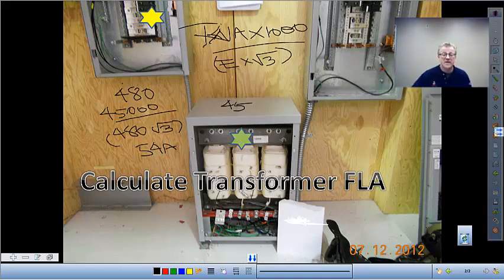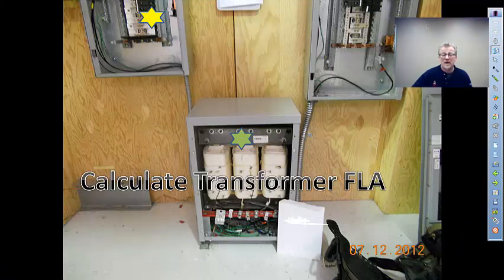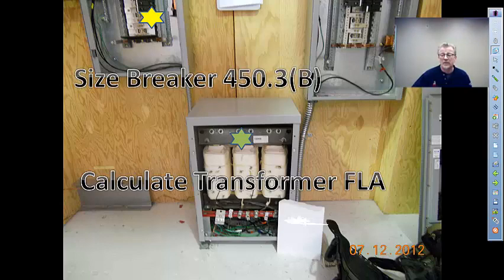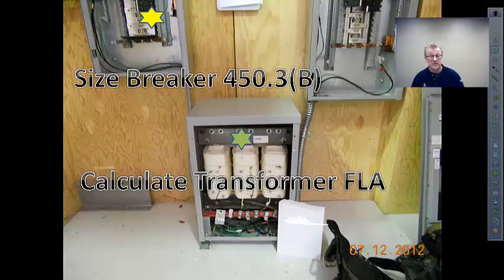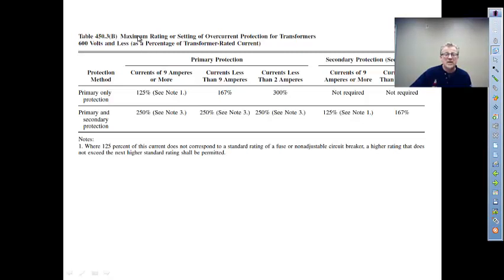While you're at it, calculate both sides. But for our discussion, we just really need the primary. Then we're going to size the breaker from 450.3(B). 450.3(B) gives us the maximum rating or setting of overcurrent protection for transformers. When we have currents of 9 amps or more with primary protection only, remember that was one of our assumptions, this 125% of the full load current of that transformer will give us a maximum. Note 1 does allow us to go up to the next higher standard rating.